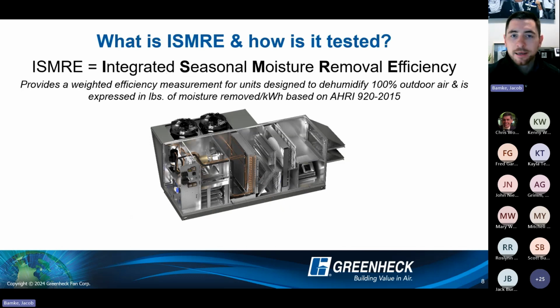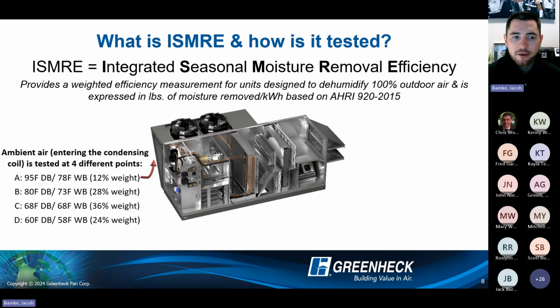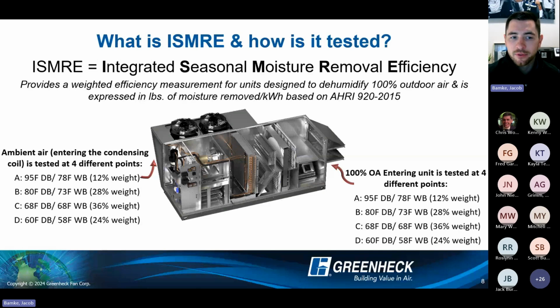On the flip side, you have ISMRE. Very similar, it's integrated seasonal moisture removal efficiency, and that looks at 4 conditions. But one thing you'll notice is that now it's truly looking at those exact same outdoor conditions entering that unit. So it's not a recirc application. We're really saying how efficient are we at removing moisture from the outside air, because this unit is a 100% outdoor unit, and this is where you need to make sure that we have this.